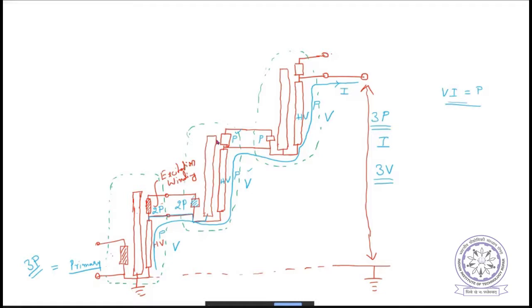Because what happens now? As long as load capacitance is small, there is no problem. But if load capacitance is high, what happened accidentally when these cascaded transformers were used to test long cables, then during testing itself, huge voltage was generated and the cables broke down. So after that, a detailed investigation was done. Why has this happened?